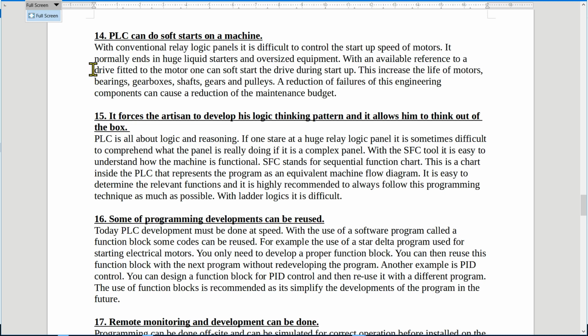Now, if you do a soft startup of a machine, it will naturally increase the life of motors, your bearings, your gearboxes, your shafts, your gears itself, and your pulleys and your V-belts. Because the machine is not shock loaded at the moment. It's not trying to accelerate from 0 to 100% all the time. It is actually accelerating in a controlled fashion without creating shock loads to your bearings and to your gearboxes and motors. And naturally your components will last forever. And if you actually connect this with speed reduction, your life will also be extended. And it is one of the benefits of a PLC that cannot be ignored.